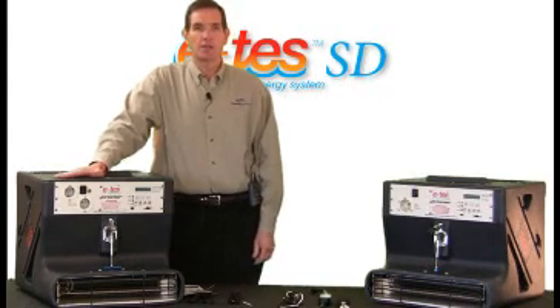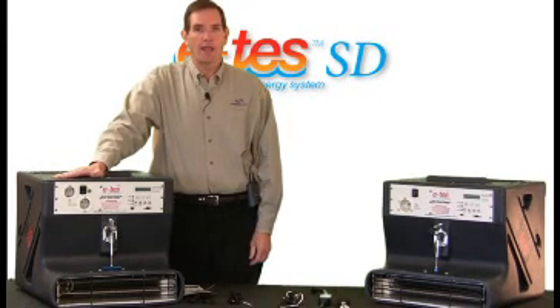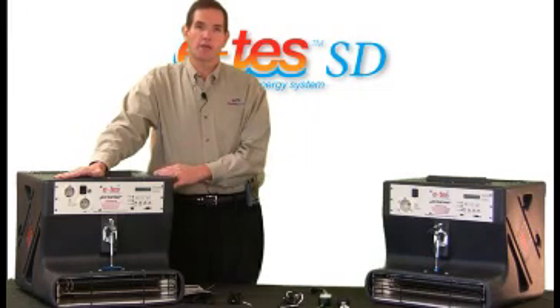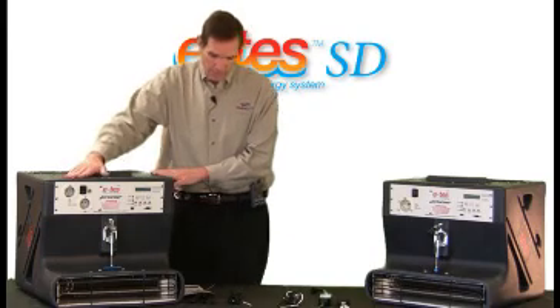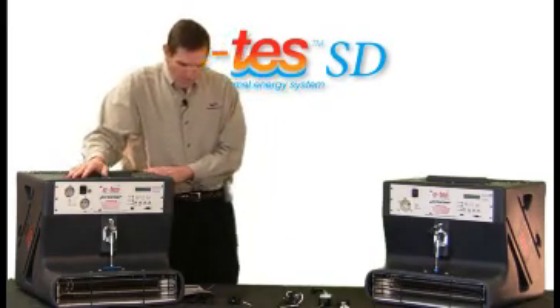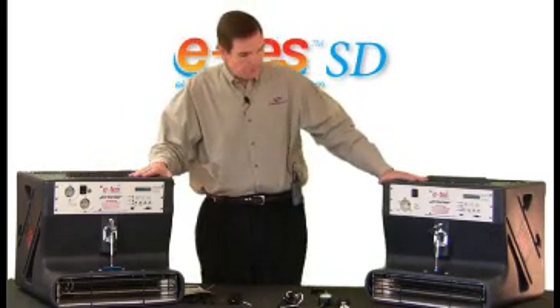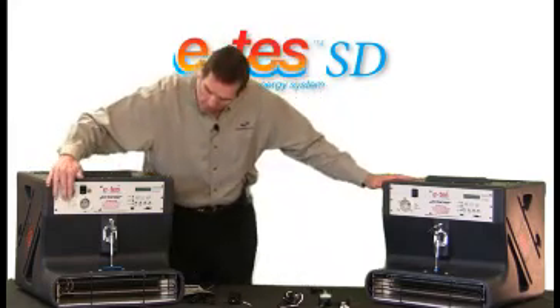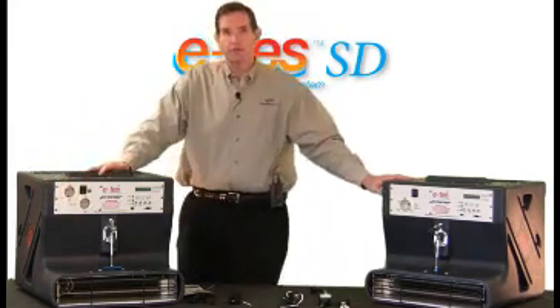This has a built-in hour meter now. It also has a built-in humidistat that will read the humidity and a temperature sensor. Those are part of the system. So again, as we go along, it's going to now not only monitor those and register those, but you can now document them and data log them at the same time. You're looking here at our two different models, and we'll leave this up to Greg a little bit more, but we have the 240 volt model, he'll show you that, and then we have the 120 volt model, which is a dual cord system here. He'll go over the operation of that in just a minute.